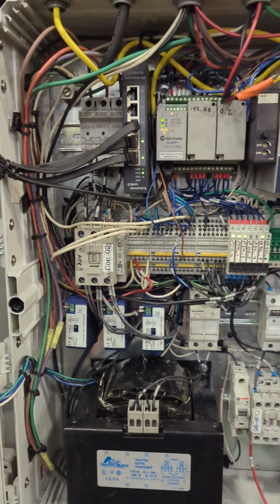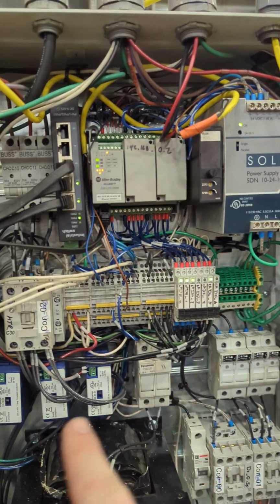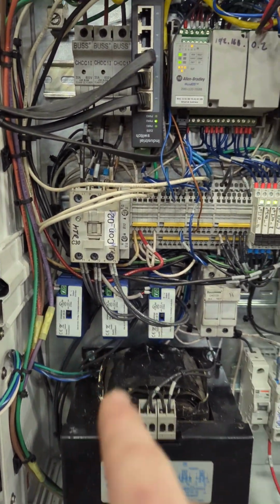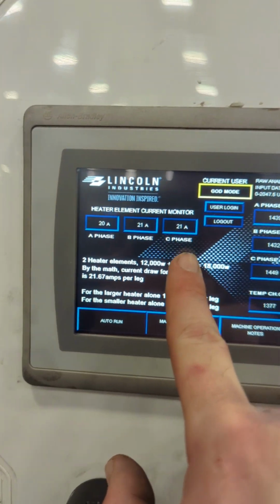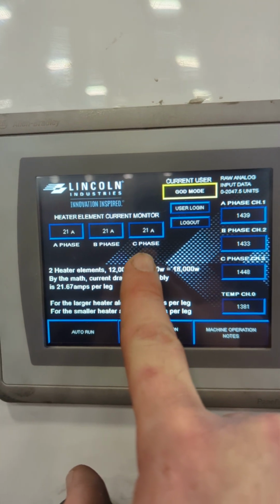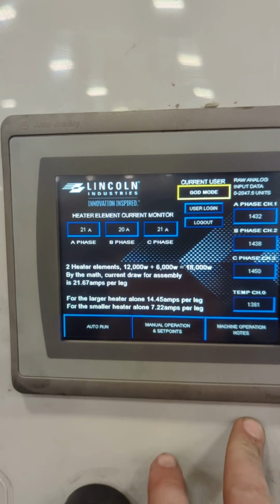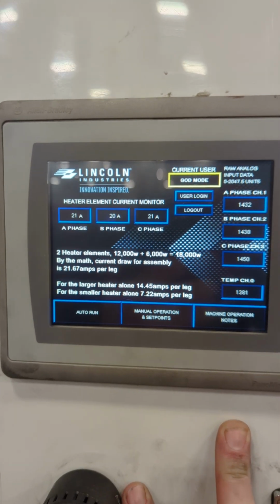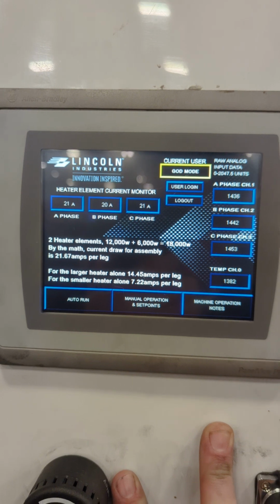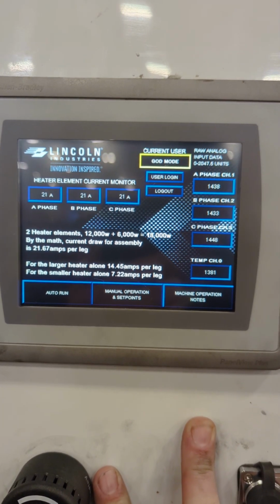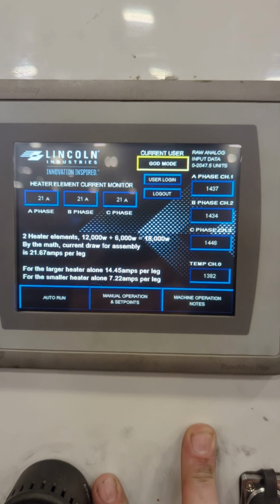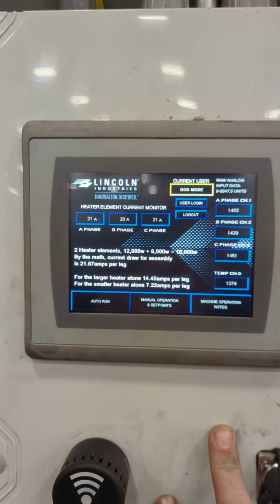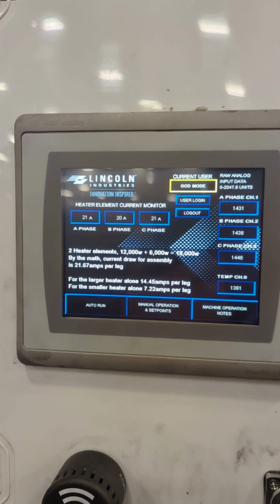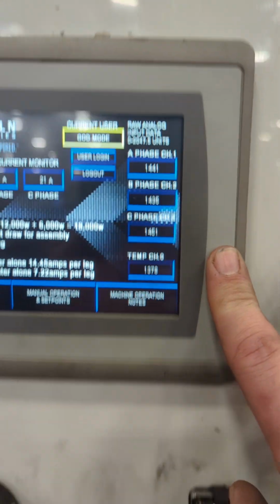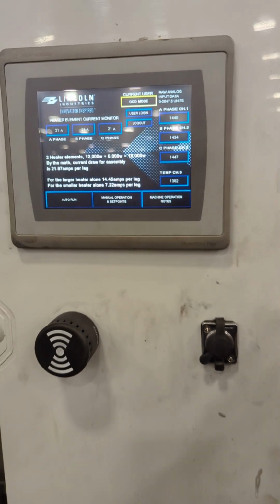Inside, you got the PLC, signal conditioner, 24 volt power source, contactors, my transducers for my heater current, and I can go in here and monitor my heater current. And I got an alarm set. If one leg drops down below 19, it'll alarm out, letting us know the heaters are bad. In that event, obviously it would fail open. Typically a heater will short, blow a fuse, we'll have to turn it back on, then it would fail open, and whoever's working on this would know that the heater's bad and we need to come and replace it.